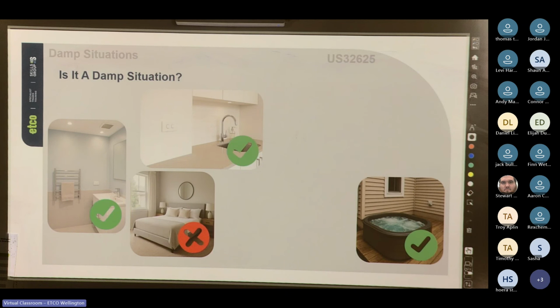Yeah, a tiny hole. Try to make it small enough that insects can't get in, but that water can get out. The other option is if you're bringing a conduit into the isolator, you bring the conduit down and then up, and you can make a very tiny slit in that corrugated conduit, and water can drip out that way. It also creates a water lock if you do it properly. You have to be very careful not to ruin the IP rating if you drill them out. Ideally, they won't get water in them if they're sealed properly, but you should always make sure.